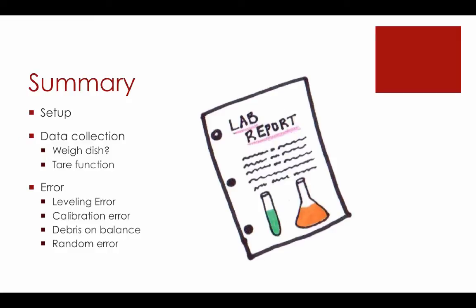To wrap things up, we had a brief discussion on how to properly set up a digital balance. We talked about the process of data collection and specifically when to use and when not to use a weigh dish, and when using a weigh dish, how to properly use the tare function. And finally, we had a discussion on how the balance can introduce error into your experiment. We talked about the error associated with not properly leveling the balance. We talked about the error associated with not necessarily having the balance recently calibrated. We talked about what error that debris on the balance scale can potentially introduce into our experiment. And finally, regardless of how much we work with this, the fact that no matter what we do, we'll always have a certain amount of random error. All of these can be used as potential talking points in your lab reports when trying to analyze how much error in total a balance may have introduced into your experiment.